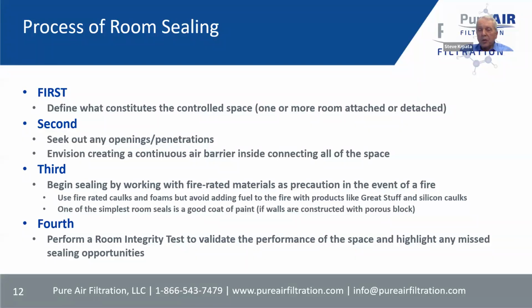We have to treat that controlled space as common areas for purposes of room sealing, and they don't have to be contiguous rooms. If they're connecting through ductwork, that can make detached rooms part of the same controlled space. So sometimes it gets trickier than you might think at first blush in deciding what the controlled space is that has to be addressed to begin with.